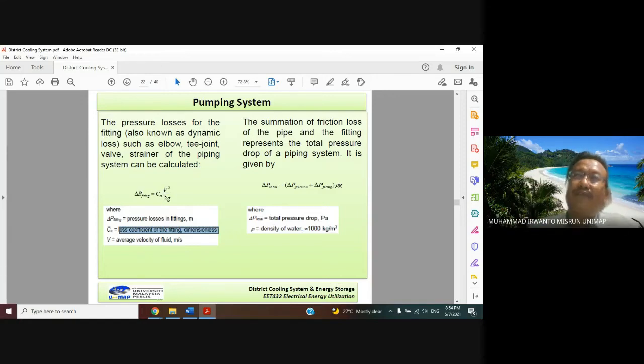So we have pressure losses from the pipe itself, and also from the fittings including elbow, T-junction, strainer, and valve. The total pressure is the summation of the friction loss from the pipe and the fitting, given by: delta P total equals delta P friction plus delta P fitting. If we convert to Pascal, we multiply by rho G.